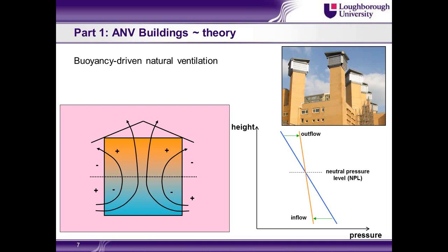So buoyancy-driven natural ventilation, then warm air rises. Each of us is giving up about 70 watts. That warm air rises, and it will find its way out of the building through any openings at high level, whether they be gaps in the construction and the fabric of the building, or whether they be purpose-provided controlled ventilation openings. So that warm, stale air will flow out of the building. As it does, it will suck in fresh air at low level. And the reason it does that is because pressure decreases with height. So the more air we've got above us, the heavier the air, and therefore the greater the pressure that's acting at a height.